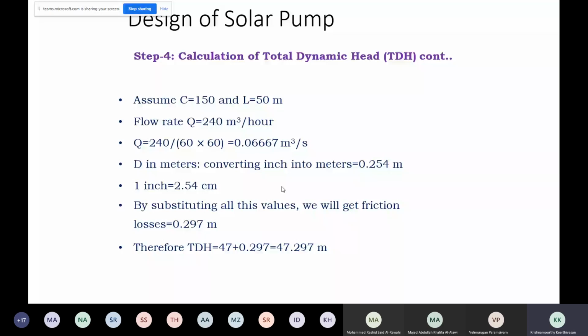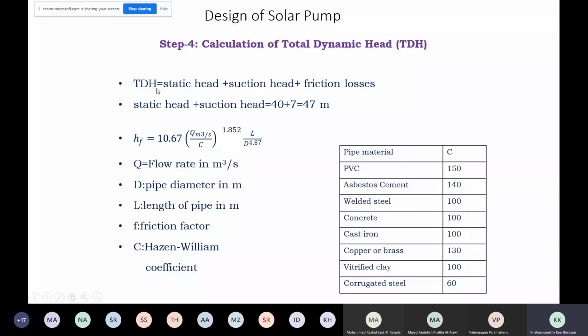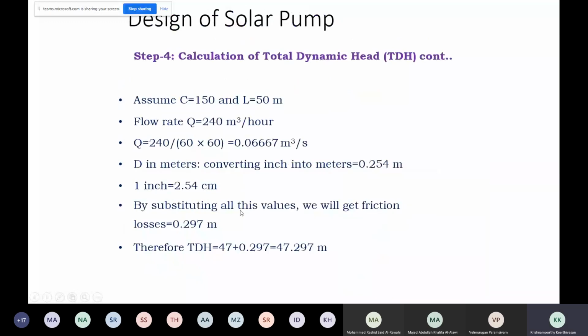So here we took 47 taking frictional losses, 47.297 like that. D is the pipe diameter, L is the length of the pipe, F is the friction factor. This Hazen-Williams coefficient, I think, is something related to civil people. I'm not good in this one. So we have calculated the total discharge head, 47.297. So that value it should pump.